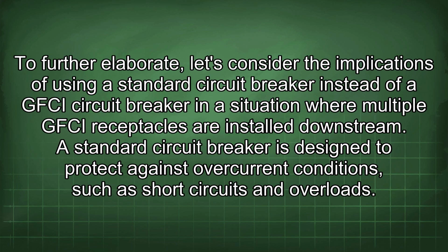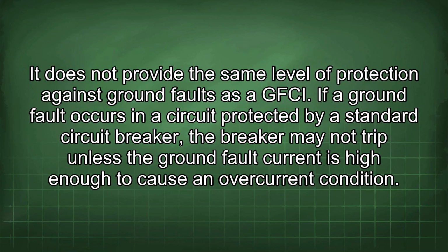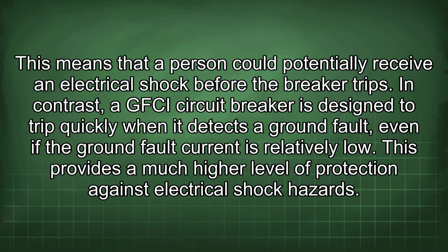To further elaborate, let's consider the implications of using a standard circuit breaker instead of a GFCI circuit breaker in a situation where multiple GFCI receptacles are installed downstream. A standard circuit breaker is designed to protect against overcurrent conditions such as short circuits and overloads. It does not provide the same level of protection against ground faults as a GFCI. If a ground fault occurs in a circuit protected by a standard circuit breaker, the breaker may not trip unless the ground fault current is high enough to cause an overcurrent condition. This means that a person could potentially receive an electrical shock before the breaker trips.